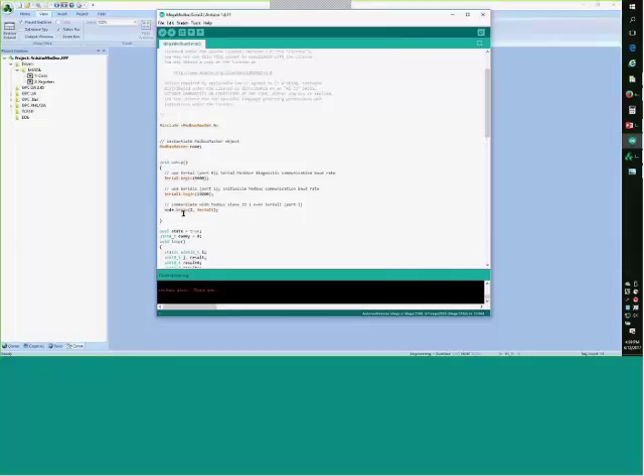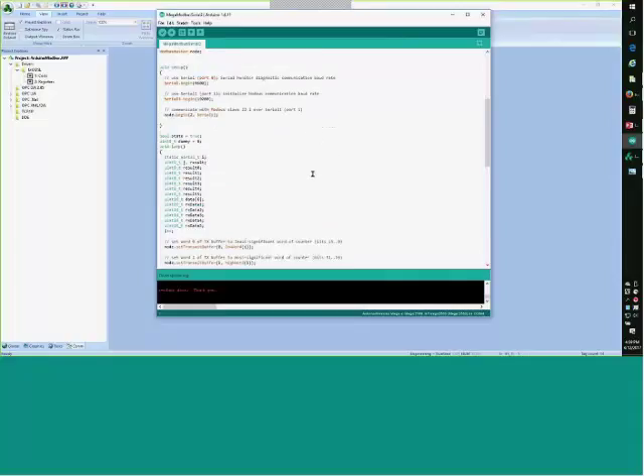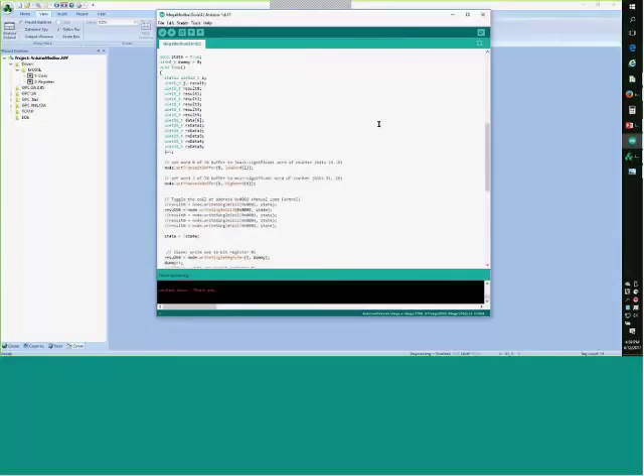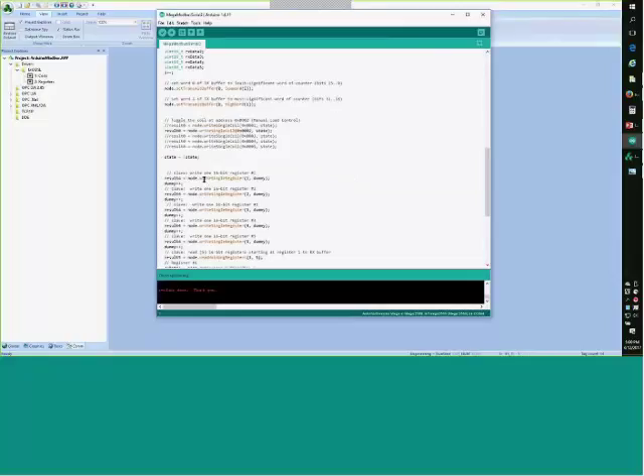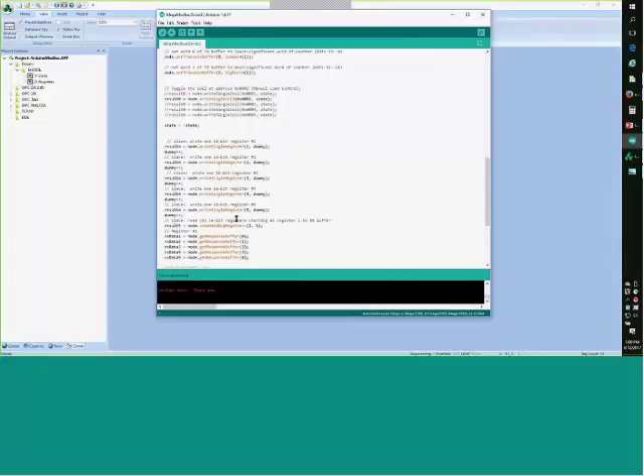The slave ID here has to match what's configured in Indusoft. This is just a test program I came up with. Here, I'm writing a single coil — that's a write single coil — and giving it a value. And here I'm writing registers as an example of writing all these individual registers with dummy values. And this shows an example of how to read the registers.